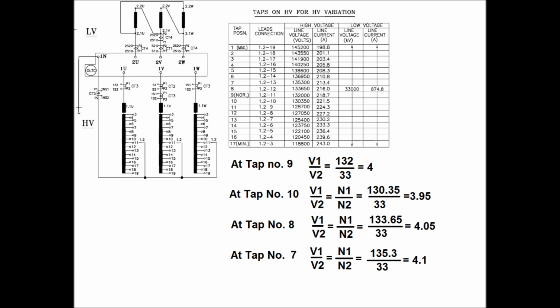From the above table, we can calculate the N1 by N2 in terms of the ratio of V1 by V2. So at tap number 9 or at nominal tap, N1 by N2 is equal to V1 by V2, which is 132 by 33, which is equal to exactly 4. At tap position 10, V1 by V2 is equal to N1 by N2 equal to 130.35 kV by 33 kV, which is equal to 3.95. At tap position 8, V1 by V2 is equal to N1 by N2 equal to 133.65 by 33, which is equal to 4.05. And at tap position 7, N1 by N2 equal to 4.1.